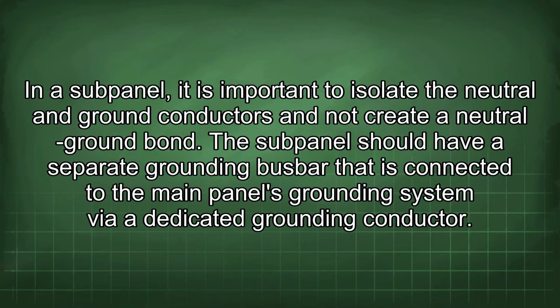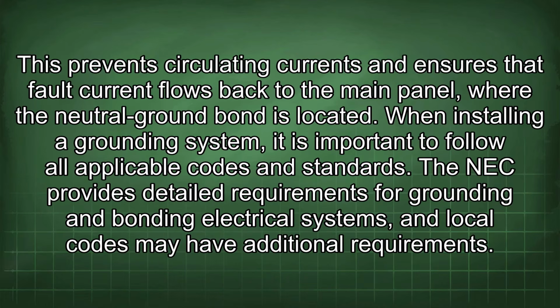In a subpanel, it is important to isolate the neutral and ground conductors and not create a neutral ground bond. The subpanel should have a separate grounding busbar that is connected to the main panel's grounding system via a dedicated grounding conductor. This prevents circulating currents and ensures that fault current flows back to the main panel, where the neutral ground bond is located. When installing a grounding system, it is important to follow all applicable codes and standards.